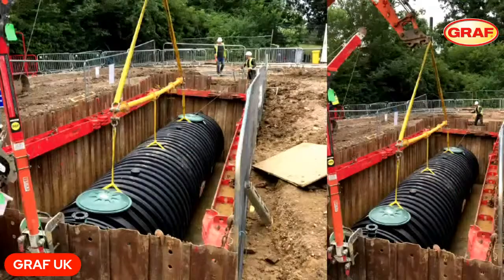So with a firefighting tank, you generally need to have a certain volume of water available during the emergency event. These typically start from around about 45,000 litres. As Callum mentioned, we installed a 52,000 litre tank at this site, so we're obviously within that restriction, just encompassing that by a few thousand litres.